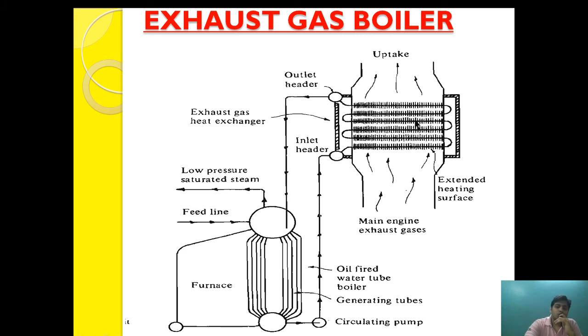From time to time, the exhaust gas boiler needs to be cleaned so that heat efficiency does not deteriorate. For that, it is blown with air, and after a specific interval — around 6 to 7 months — it is also cleaned with water. The cleaning water is collected in a soot tank and ultimately passed through the OWS (oily water separator) before being discharged overboard.